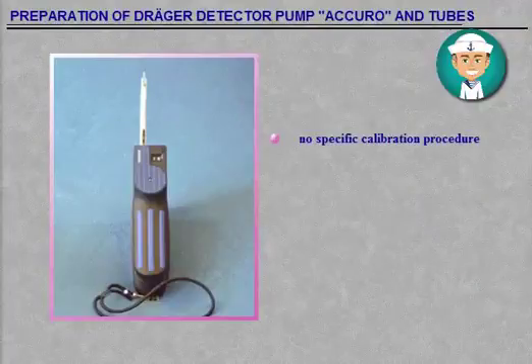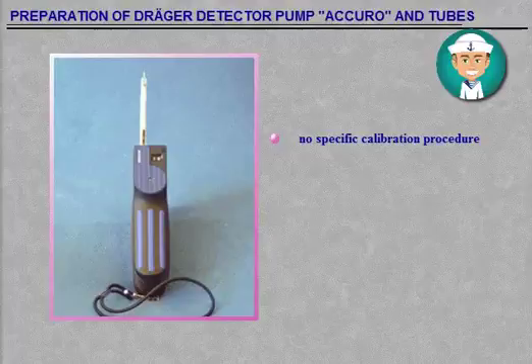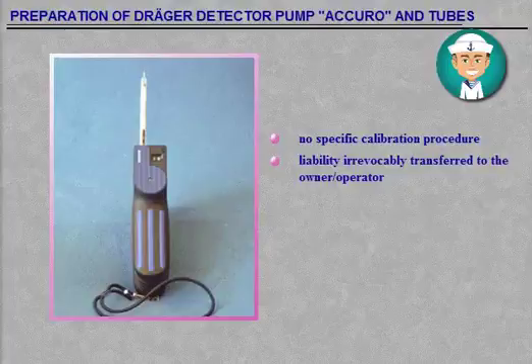There is no specific calibration procedure for the Dräger Multigas Detector Accuro and tubes. Any use of the apparatus requires a full understanding and strict observation of the instructions for use of both the pump and the indicator tubes. The liability for the proper function of the apparatus and use of tubes is irrevocably transferred to the owner or operator, to the extent that the apparatus and tubes must be operated according to the instruction books.